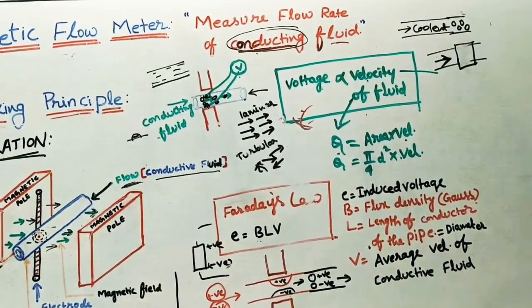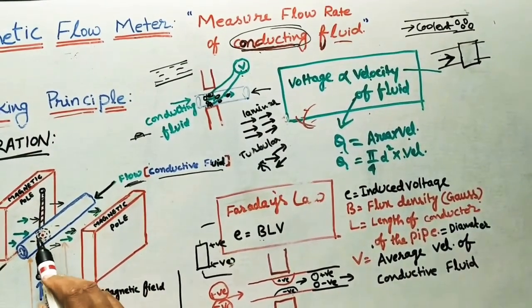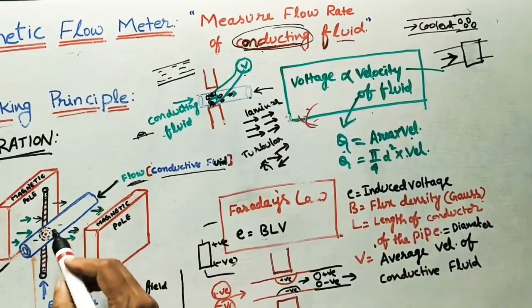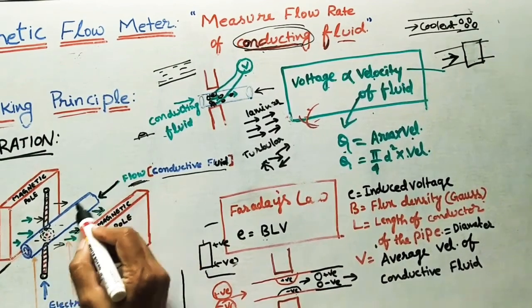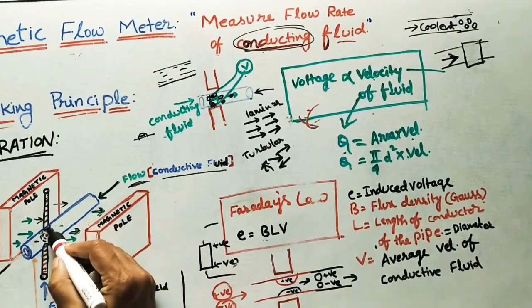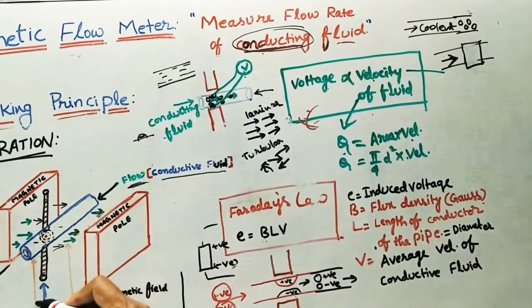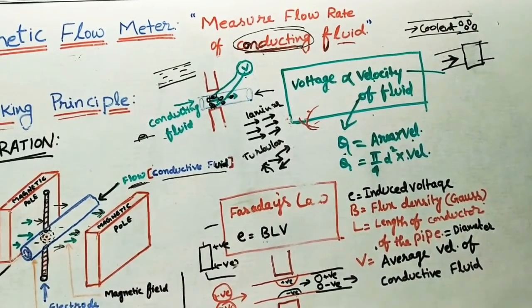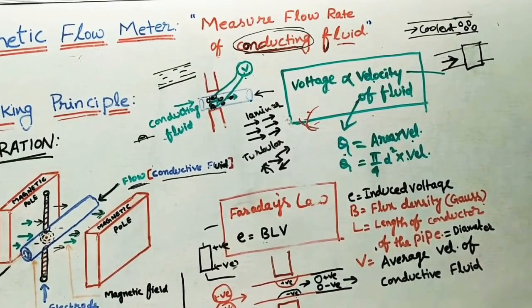Limitations: it does not give the correct value for non-conducting fluid. The fluid should be completely full in the pipe — if the fluid level is less, it gives the wrong Q value. Sometimes air and gas bubbles form in the flow, causing the generated voltage to give the wrong value. Also, the electrodes can get coated with the flowing material — for example, grease or oil can coat the electrode surfaces — so the electrodes must be regularly cleaned and maintained.